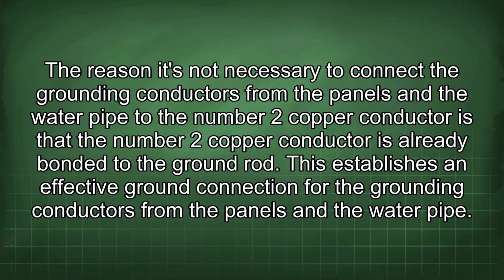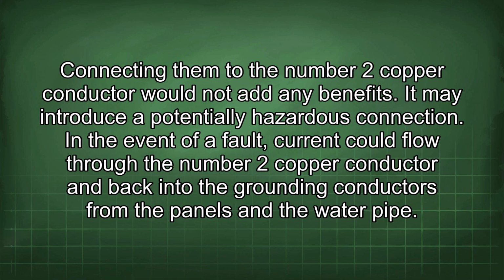The reason it's not necessary to connect the grounding conductors from the panels and the water pipe to the number 2 copper conductor is that the number 2 copper conductor is already bonded to the ground rod. This establishes an effective ground connection for the grounding conductors from the panels and the water pipe. Connecting them to the number 2 copper conductor would not add any benefits.